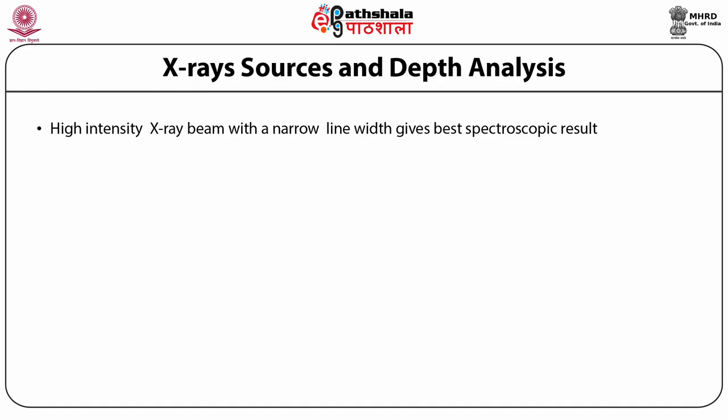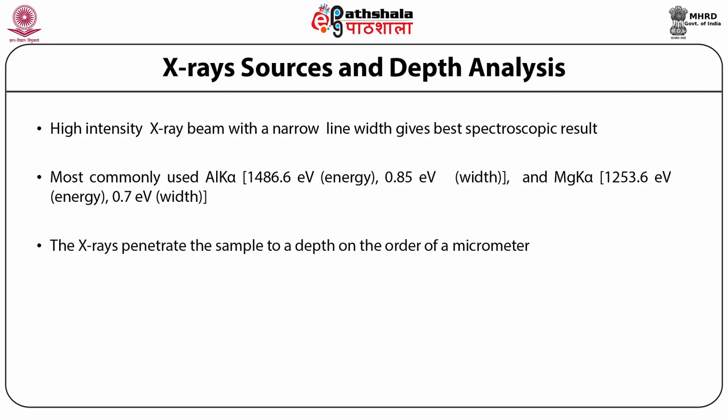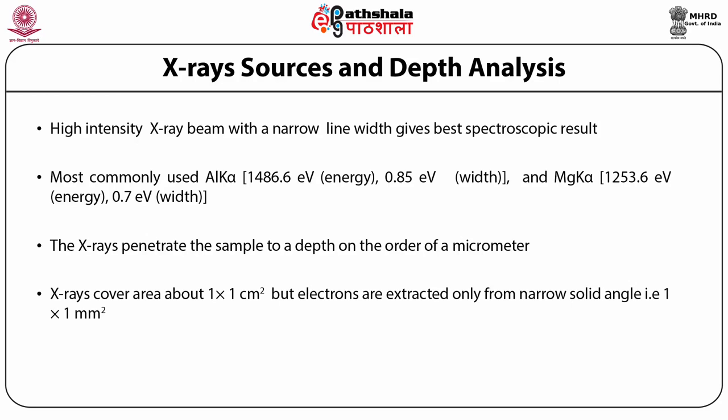In XPS, a high intensity X-ray beam with a narrow line width gives the best spectroscopic result. The most commonly used X-ray sources are aluminum K-alpha and magnesium K-alpha, both with line widths less than one electron volt. X-rays can penetrate the sample to a depth on the order of a micrometer and cover an area of about 1×1 square centimeter, but electrons are extracted only from a narrow solid angle of 1×1 square millimeter. Useful electron signal is obtained only from a depth of around 1 to 10 nanometers of the surface.